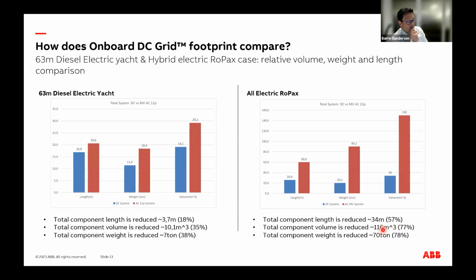Again, much due to the transformers, but also in this case the charging is medium voltage. With DC we can charge more because we don't have reactive current, so we can charge more on the same plug. We manage without the charging transformer for the medium voltage. It's an extreme case, not normal, but there are cases like this. This is an all electric ferry, and it goes for many of these. At least what I've seen out there in the last couple of years, on these kinds of vessels, it's only talking about DC systems, even the bigger ones, because it makes sense, both for efficiency and for equipment and capex.